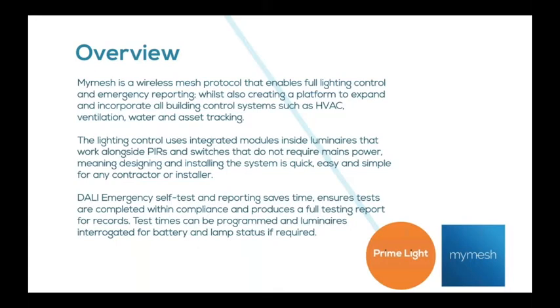So that's just a very brief overview. Effectively, it's a node mounted inside a luminaire. Then you bring in your control functionality, whether that's PIR or manual control via switch. And if you've got emergency, all it needs is a DALI self-test emergency module, and off you go. Very simple, very easy to use.